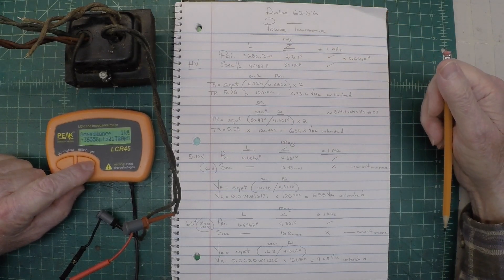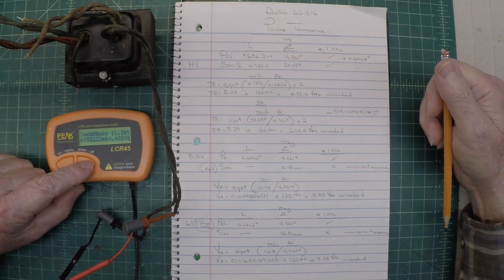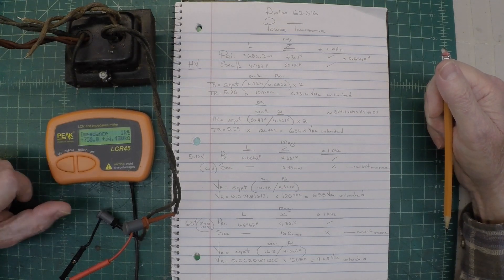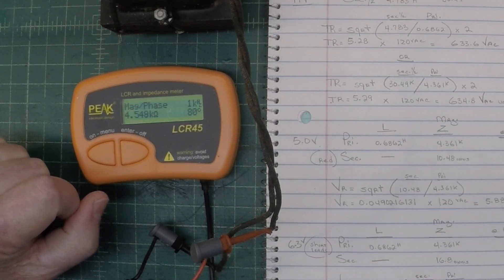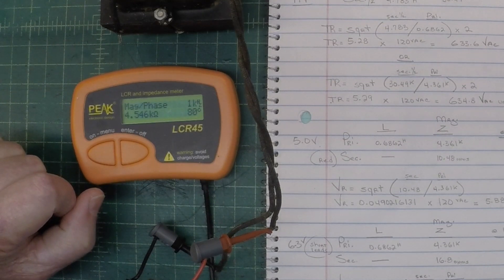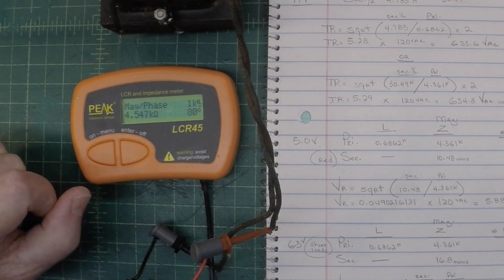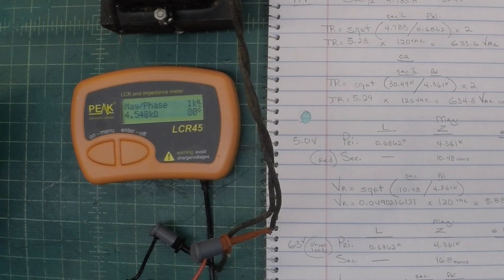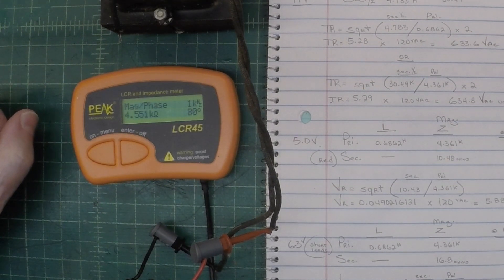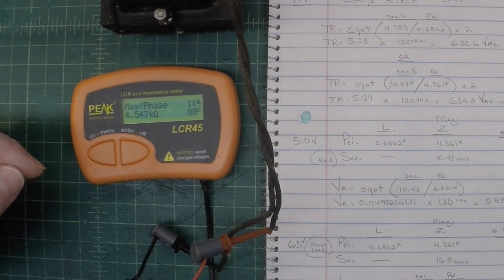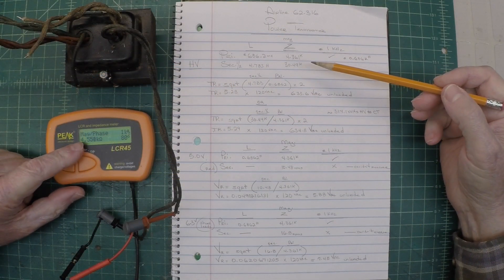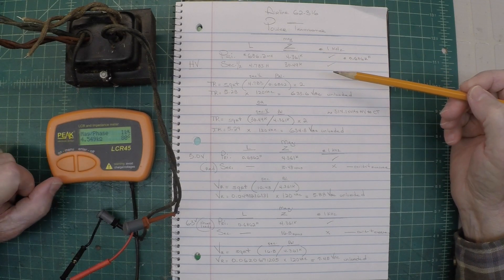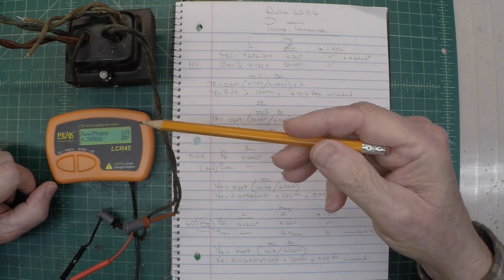Now, this particular meter has a pretty cool feature. You can see the calculated impedance, but there's another result here that you can leverage, and you can see the magnitude and phase. If you look at the magnitude, the way they define it in the instrument is the impedance is the real impedance in addition to the imaginary parts of impedance of the component under test.